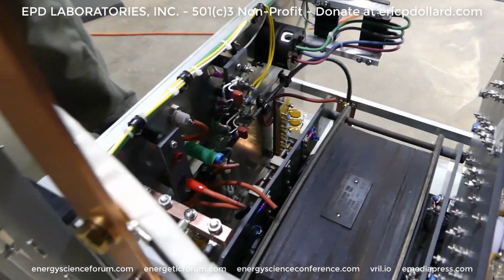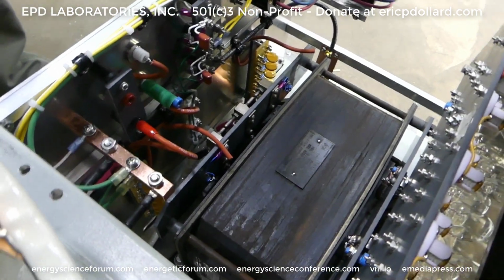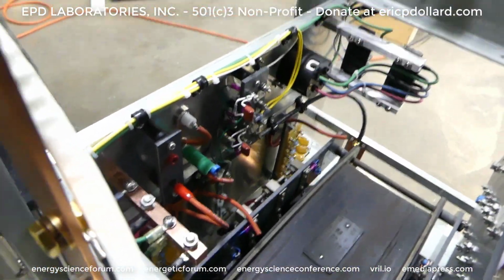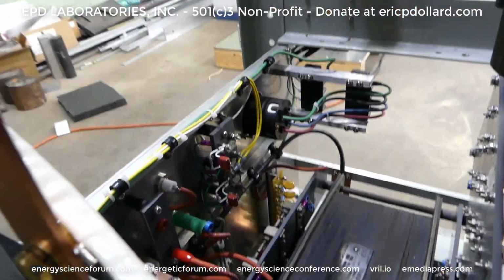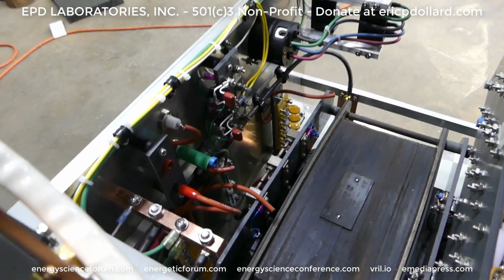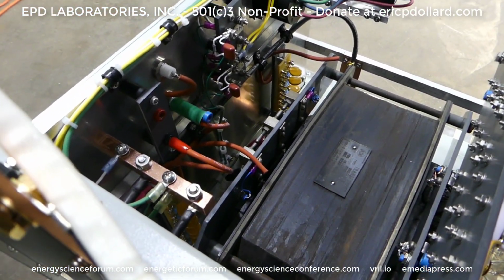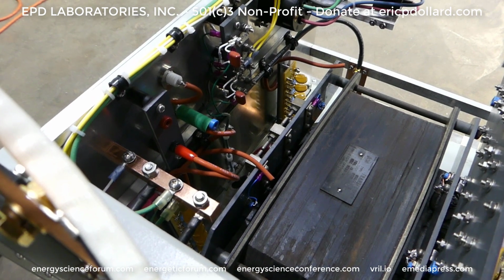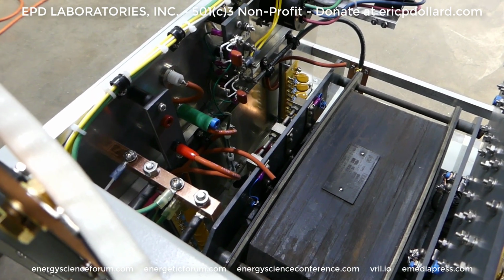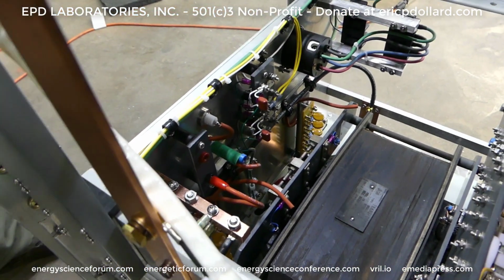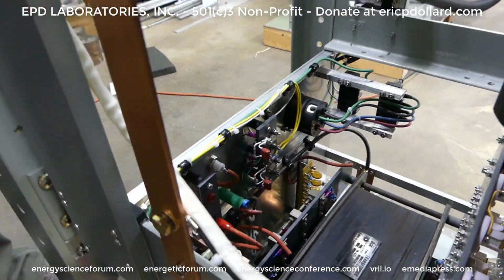In this type of configuration, there's no way that any extraneous circulating currents can get in between the chassis or the ground systems or in the rack. Even if the power line shorts to the case or whatever accidentally, none of that current will flow through any of the metal structure. It'll all be taken away by the ground system, minimizing damage to other pieces of equipment.